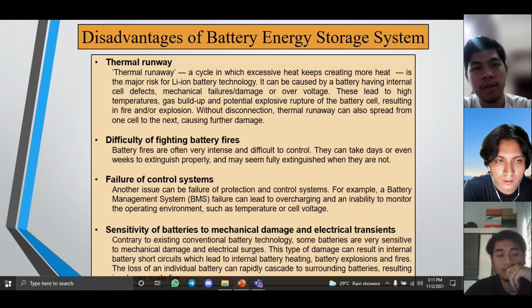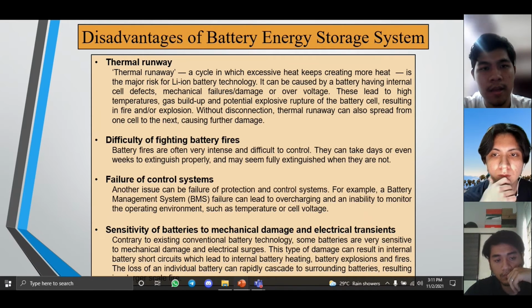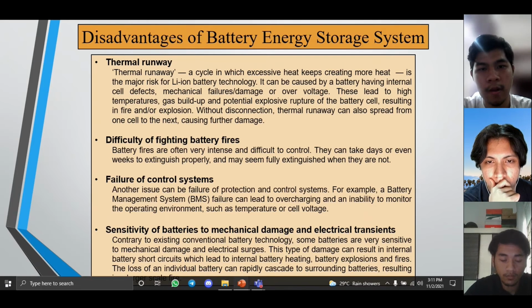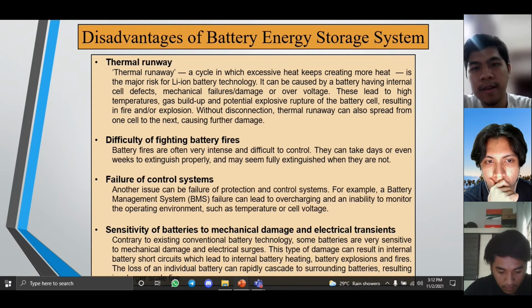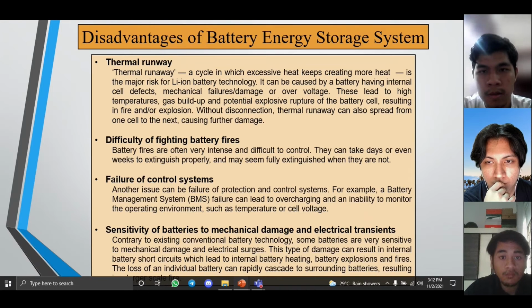There are also a few disadvantages of BESS. One is thermal runaway, a cycle in which excessive heat keeps creating more heat, a major risk for lithium-ion battery technology. It can be caused by internal cell defects, mechanical failures, damage, or overvoltage. This leads to high temperatures, gas build-up, and potential explosive rupture of the battery cell, resulting in fire or explosion. Without disconnection, thermal runaway can also spread from one cell to the next, causing further damage.